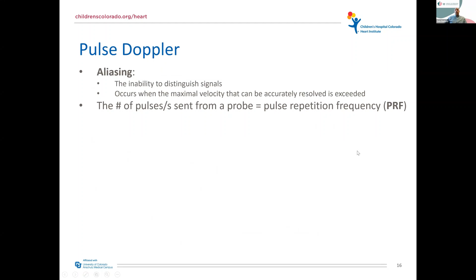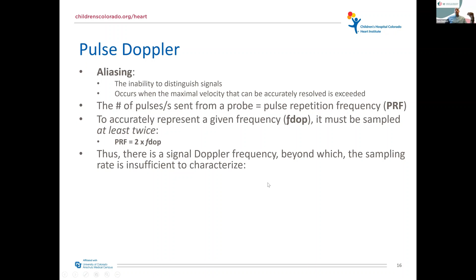The number of pulses that come out of the probe per second is known as the pulse repetition frequency, or the PRF, okay? To accurately represent any frequency that we're trying to measure, the pulmonary valve, the pulmonary vein, the mitral valve, we're going to call that the frequency of the Doppler, FDOP. We have to sample that at least twice in order to determine what that frequency is. So that relationship is PRF equals 2 times that frequency. So there is a signal Doppler frequency, some velocity of the aortic valve, beyond which you can't actually characterize it because it's moving too fast. That's the Nyquist limit.